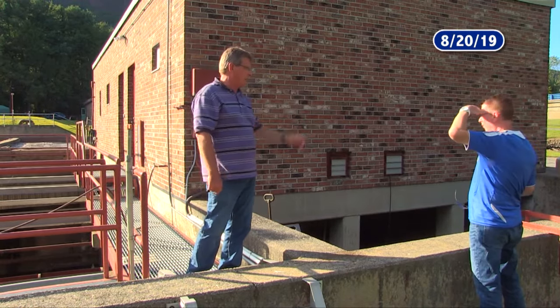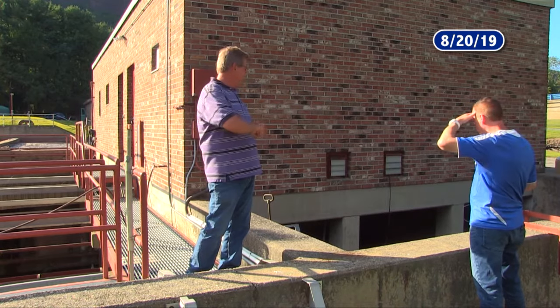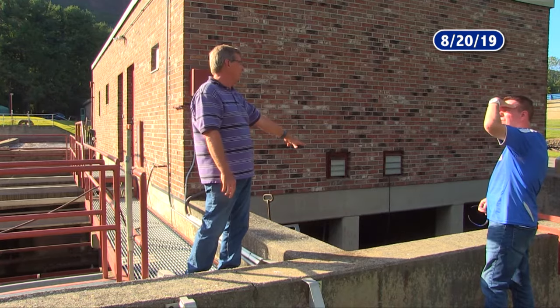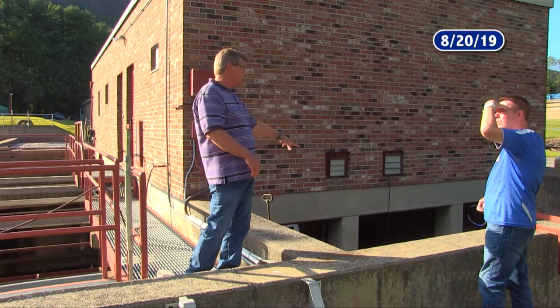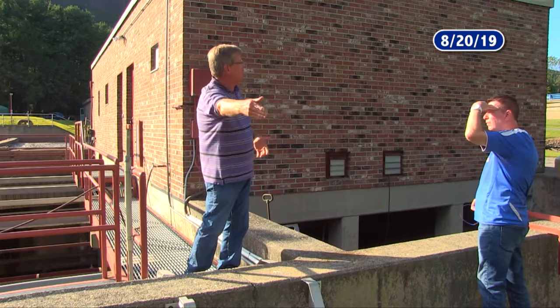And you have a question. So that's just the residence time? The residence time, yes. So the higher the flow is, the shorter the time is in this tank, too. So when the flow picks up quickly, sometimes we'll have to make a quick adjustment on the chlorine, because there's like a two-hour lag when you make an adjustment before you actually see it.